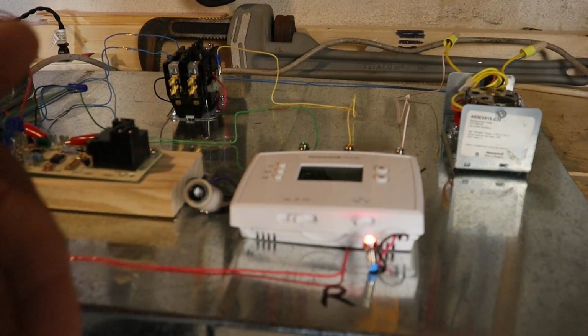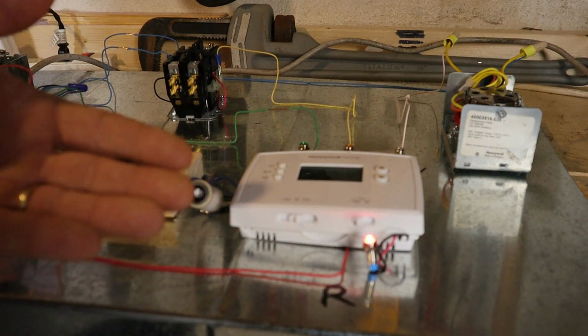Now, if you have a grounded transformer with a grounded secondary, one thing you can do is disconnect that ground from the metal and actually turn it into a floating circuit. At that point, you can see if the fuse is still blowing, which will tell you whether it's going to be a grounded wire or a bad component.